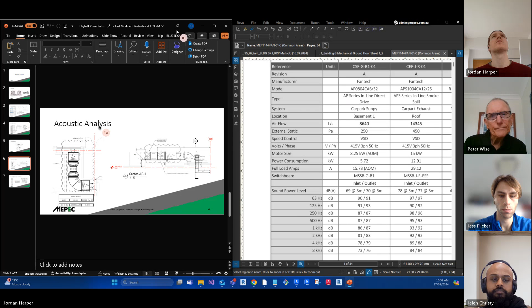The schedule's here. So this supply fan, the basement one, see here the sound level. Yeah, so those sound power levels are fairly high. The dBA, the overall sound pressure level, is 69. So yeah, I think you would need to do a calculation on that.